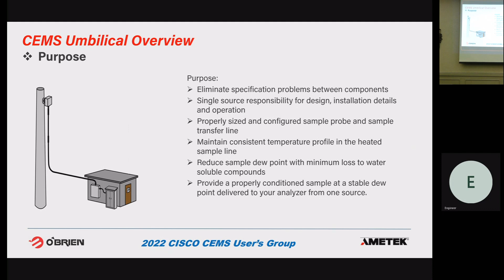Over 50 years, this shows some of the other product lines, our instrument enclosures. This is our main facility in St. Louis, Missouri. So we've got tubing bundle and then the enclosures and the instrument stands, like I said. If anywhere along the way I'm going too fast and have questions, just stop me like you have everybody else. So what's the purpose? Everybody knows it's to bring that sample from the probe, bring it down the stack, and deliver it to the analyzer equipment and keep it at a specific temperature, above a certain temperature.